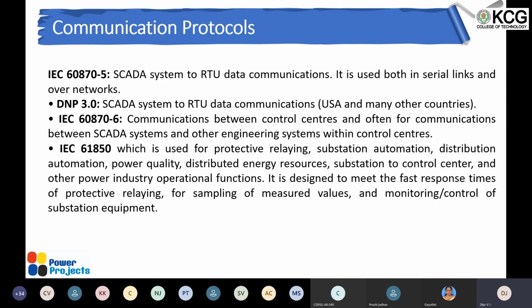So when we talk about protection communication, these are the main protocols, which I'm not going into detail: IEC 60870-5, DNP 3.0, IEC 60870-6, and the most common protocol nowadays, IEC 61850, which we can utilize not just for monitoring but for control, protection, interlock and tripping. It can be used in the scheme also. Generally, with other protocols we are not doing that, but with IEC 61850 the speed of the GOOSE signal is very fast, and it can be used for interlocking or control circuitry also, in order to reduce the actual physical, metallic cabling. So those are the protocols.